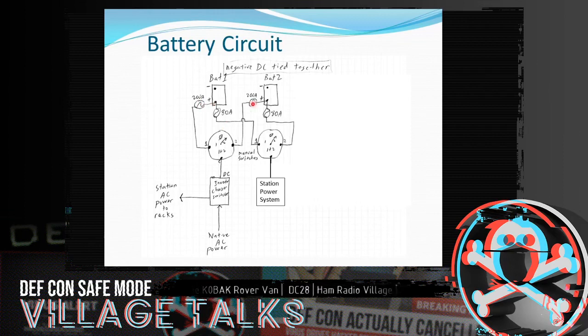200 amps come off of each battery for the inverter charger to give it enough power to supply 3 kilowatts of AC power. And then the 80 amp circuit coming off of each battery goes to this switch and then to the station power system here.